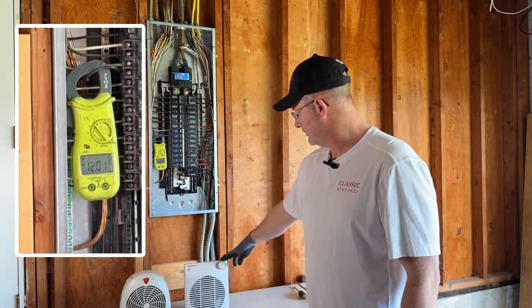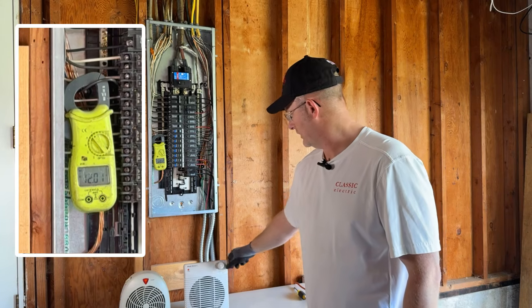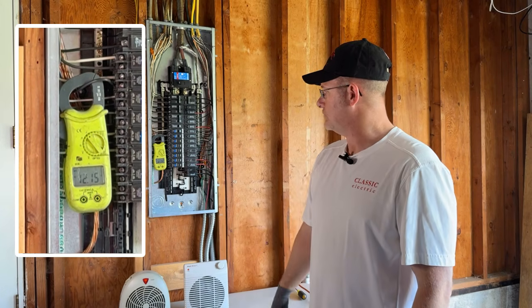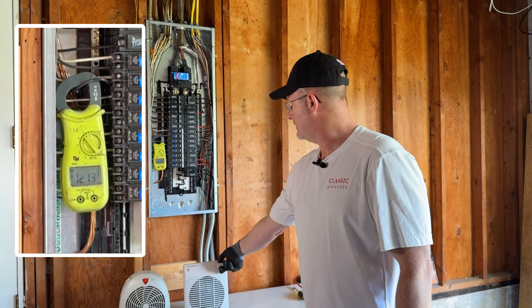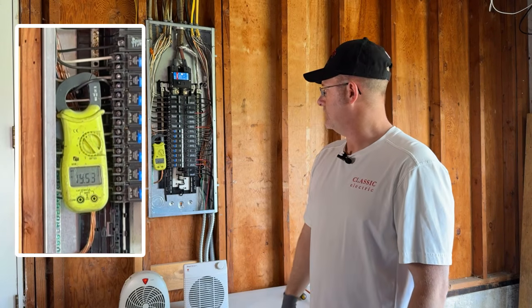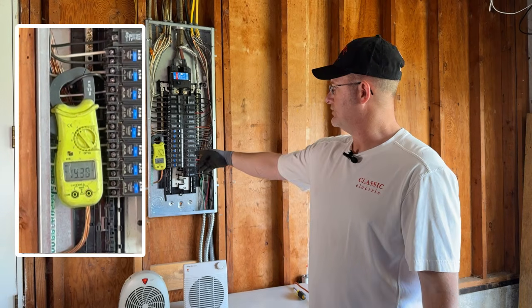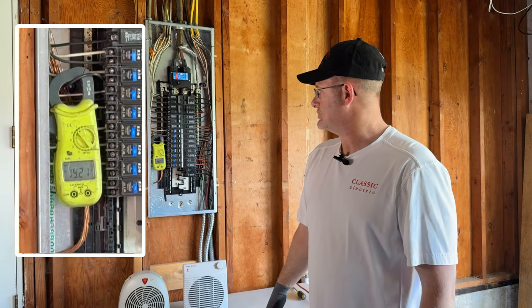Now this particular heater has a fan, it has a low, and it has a high. It has no medium. So we're going to go right to here and turn on the fan. And as you saw on this one, it doesn't draw that much more. It barely even nudged. Now we're going to go ahead and go low. Holy moly, now we're at 20. So you've got a 20 amp circuit and it's drawing 19.3 on this particular circuit.